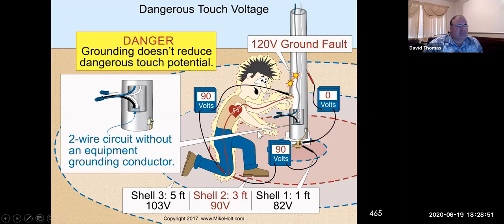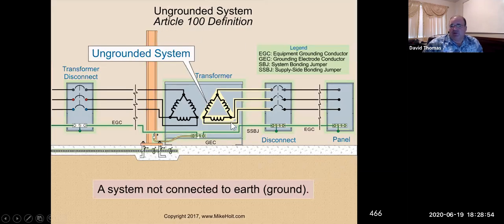And we're still kind of defining things. This one: what is an ungrounded system? You can see here, this system is not connected to Earth. We still ground all our boxes and everything else, but if a hot did touch the frame, nothing would happen. It would have nowhere to go, because there's no way for the source, like the equipment ground, to get the current to flow back into the system. So we would not have any current flow at this point.